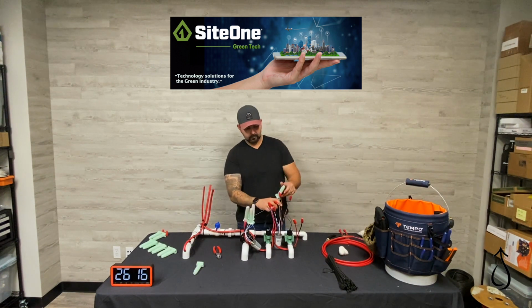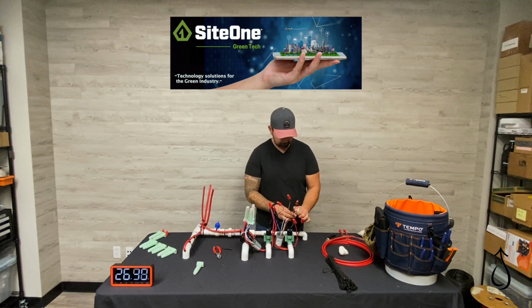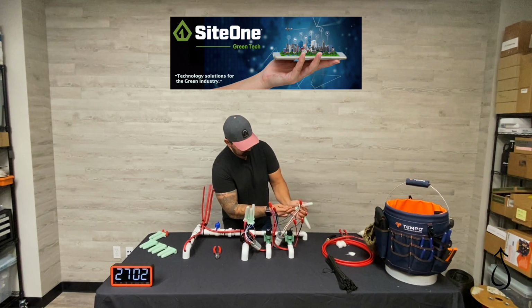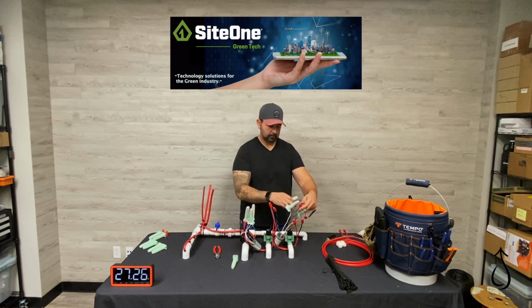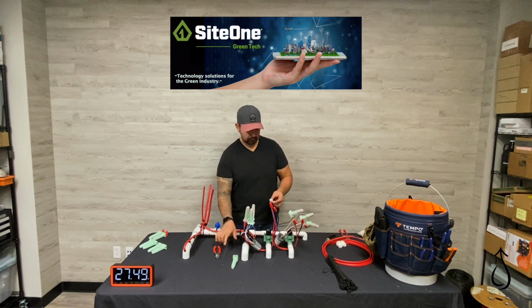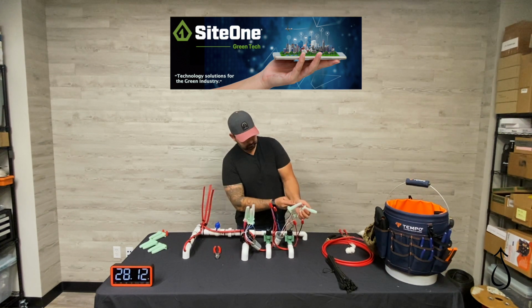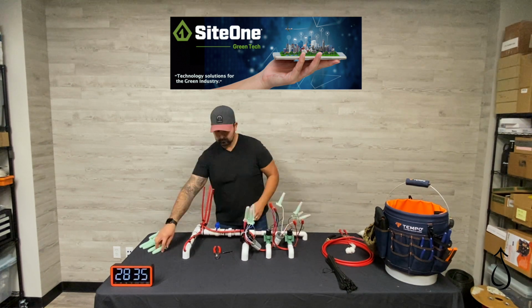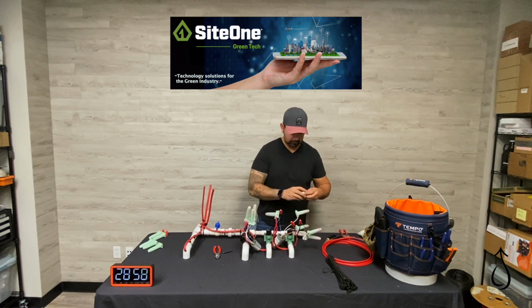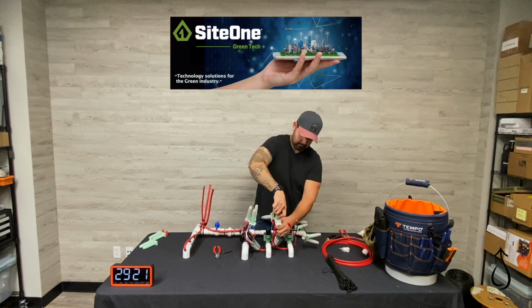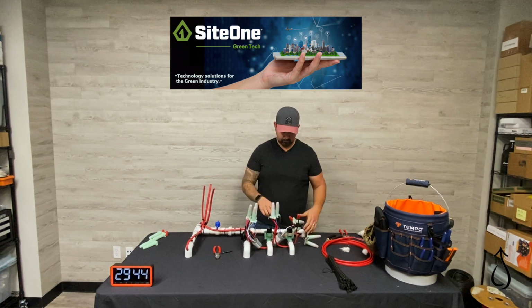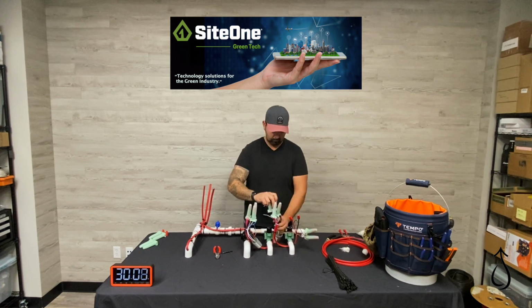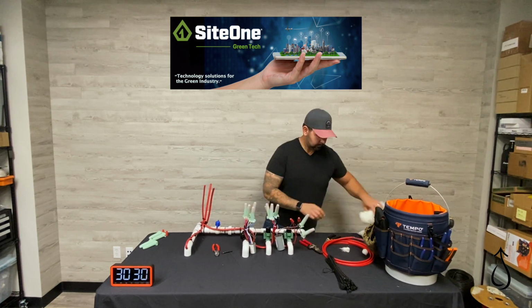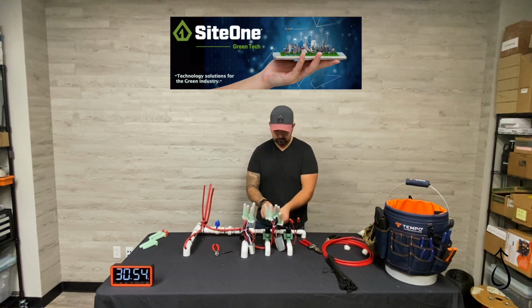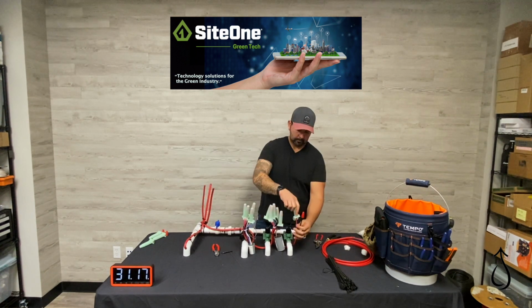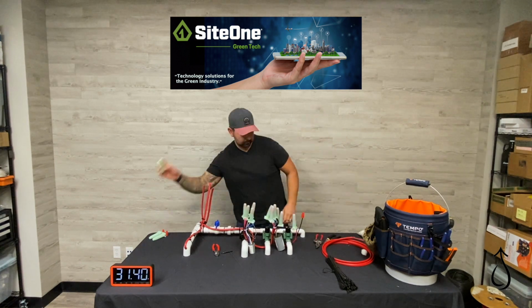In the past, I have seen dielectric grease weep out of these caps in hotter climates, which is why I use cotton balls to help, quote-unquote, slow down that dielectric grease. If these splices were to be, quote-unquote, upside down, my concern would be for the air within the once dry wire nut to rise and allow the non-conductive dielectric grease to settle within that once dry wire splice, which could make a good splice potentially a bad one. With these splices all zip tied vertically, with the dry wire nuts towards the top, the cotton balls help to create a seal to keep the dielectric grease within that splice cap.